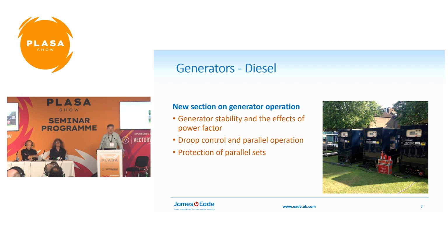The current way of getting around that is to just add load banks on, which isn't the most efficient. So the use of battery storage and similar is also coming to the fore. There's a bit of content around droop control, parallel operation and protection, and what to consider when designing systems to operate in parallel.